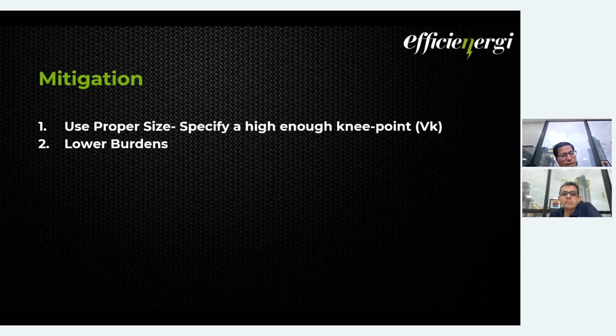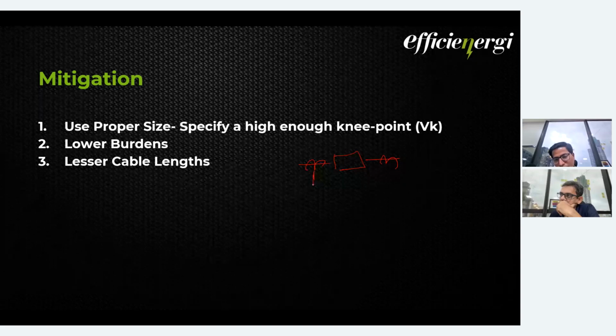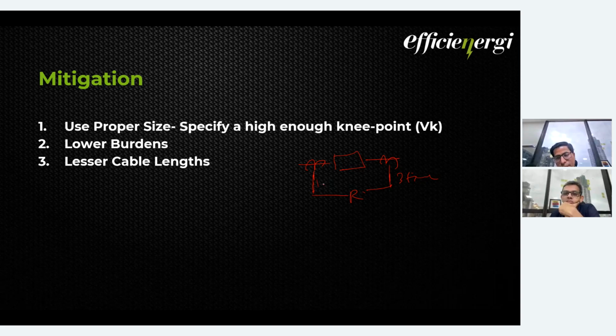The second thing is that you should lower the burdens. Lowering the burden means you can use low burden relays. That is where you can reduce some saturation. Another part of the burden is lesser cable lengths. In one of the projects where I worked, on the same differential everything was the same, but the cable length of this differential relay was almost 3 times that of this one. This is 1 time, so this is 3 times. Because of this, there was a maloperation. So these small points can lead to saturation and maloperation of the relays. So use lesser cable lengths, or have equal characteristics of the CTs on all the phases, which you have to check.